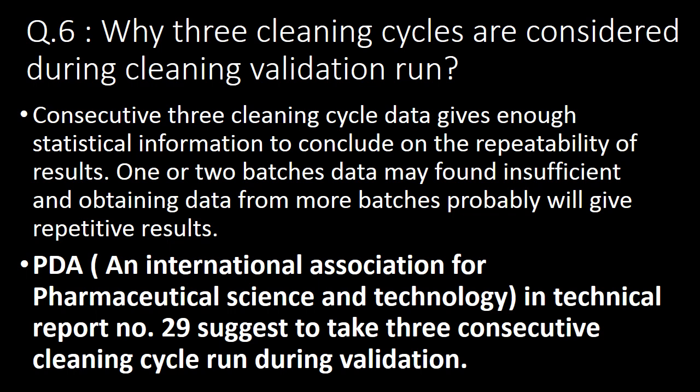The next very frequently asked question: why are three cleaning cycles considered during a cleaning validation run? Consecutive three cleaning cycles data gives enough statistical information to conclude on the repeatability of results. One or two batches of data may be found insufficient, and obtaining data from more batches will probably give repetitive results. Additionally, PDA in technical report number 29 suggests taking three consecutive cleaning cycle runs during cleaning validation.